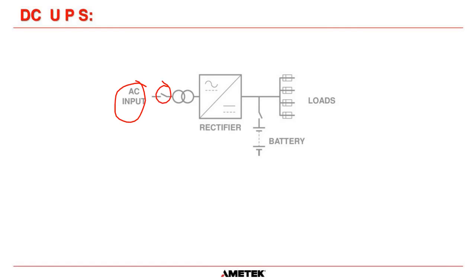You're usually going to have an AC input breaker, so you can disconnect the power to the charger. Then, in an industrial charger system, you're going to have an isolation transformer. And then you're going to have your rectifier bridge, your bridge that turns your AC into DC. And then that comes out on this bus here. That's going to be your DC bus.